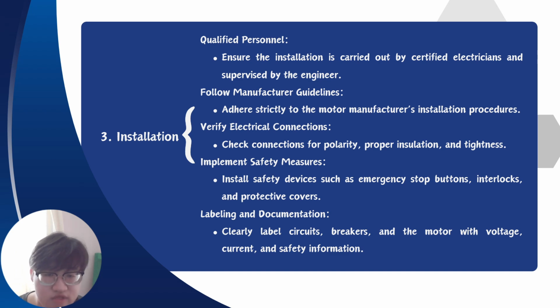Next, implement safety measures. Install safety devices such as emergency stop button, interlocks, and protective covers to prevent an emergency situation from happening. Last, labeling and documentation. Clearly label circuit breaker and the motor with voltage, current, and safety information to give an easy way for other engineers or technicians to check or do maintenance.